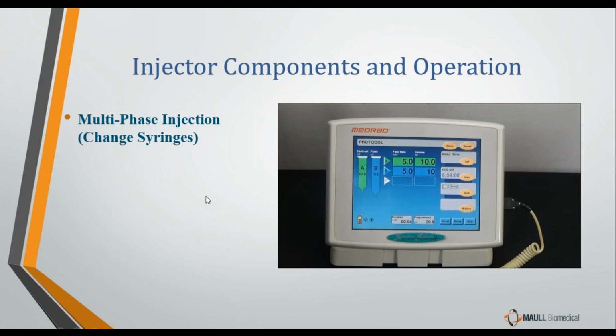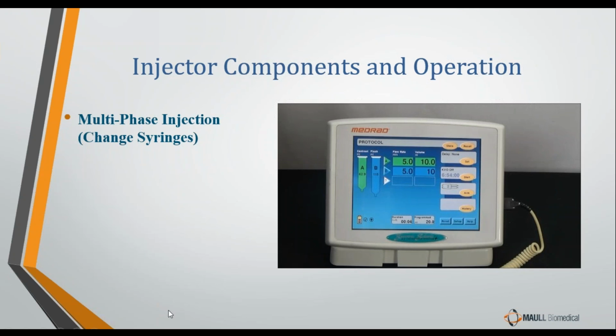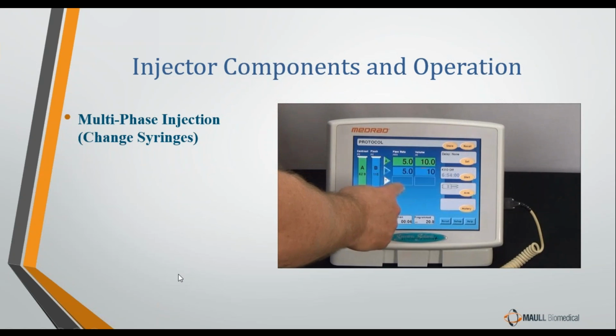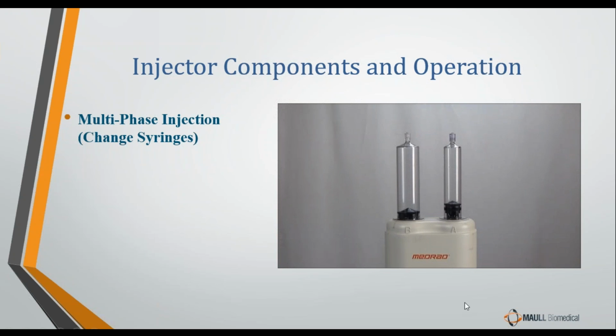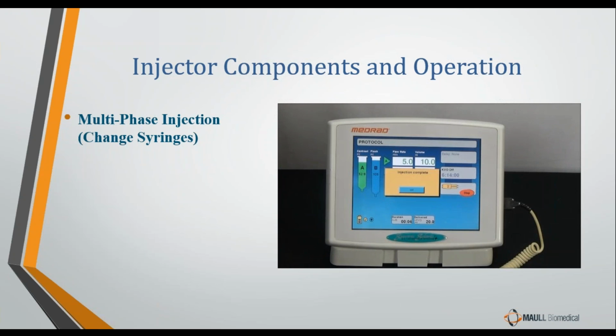And the other reason we would program a multi-phase injection is if we want to change syringes. Here we are starting off with our contrast fluid, flow rate of 5, volume of 10. We want to switch over to the saline syringe, flow rate of 5, volume of 10. So when we perform this injection, arm it. Where am I at? There we go. Confirm. Perform the injection. Now we are starting off with contrast, and it automatically moves to saline without the operator having to hit the button multiple times. And the injection is complete.